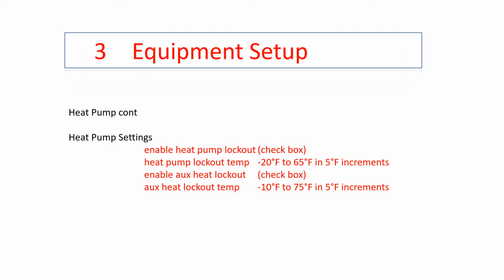The heat pump settings continued. Here's where we'll see our heat pump lockout, which is the check box you'll have to check and choose what temperature to lock out your heat pump on. Keep in mind we do have limitations right now depending on the line set lengths. You're going to want to lock that out at 15 degrees if you have a long line set length. We also have the auxiliary heat lockout, so it'll disable the auxiliary heating system above the temperature you set. So if you set it for 60, that's heat pump only from 60 and above, the auxiliary will stay locked out, including during defrost mode.